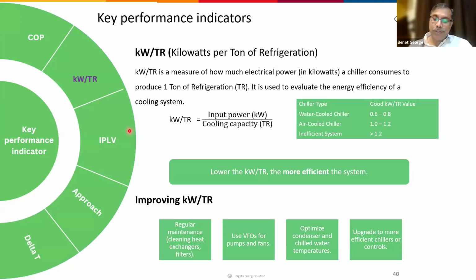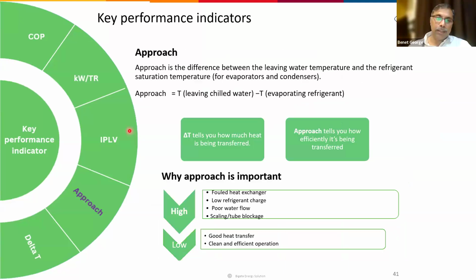You can also check the actual efficiency of the chiller by doing a chiller audit. Then we get to see what the approach is. Approach is the temperature difference between the water temperature and the refrigerant saturation temperature. If the approach is high, that means the heat transfer is not effective and we are losing energy. So then we have to see whether any scale formation is there or not. If scale formation is there, it has to be cleaned.